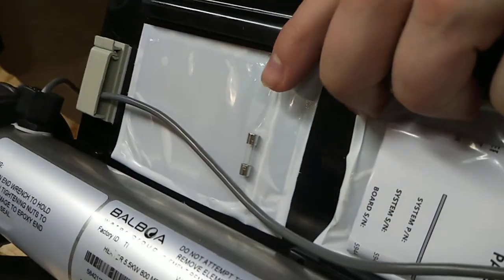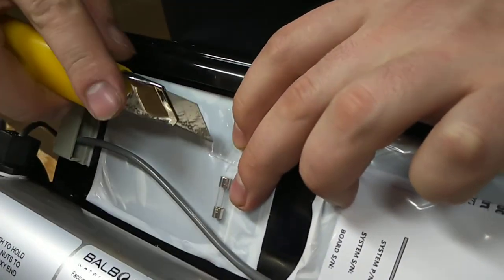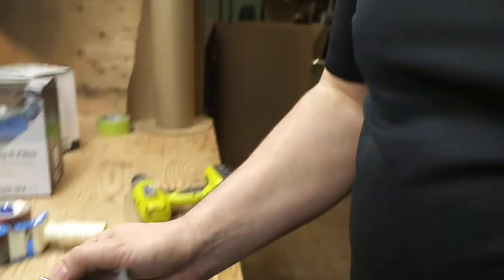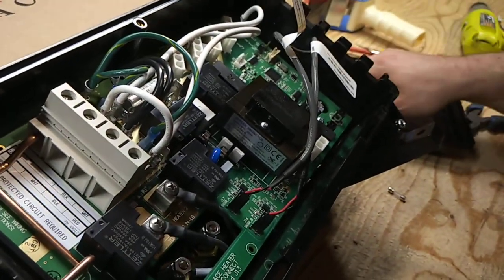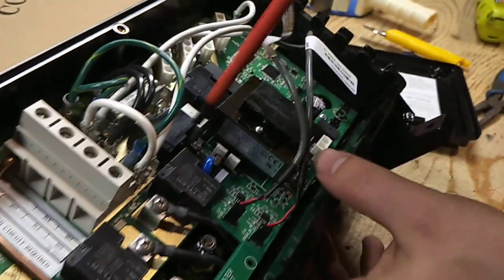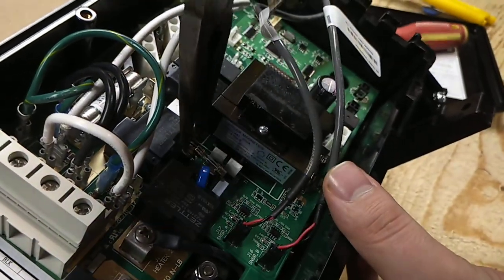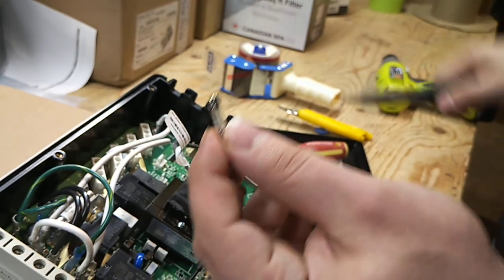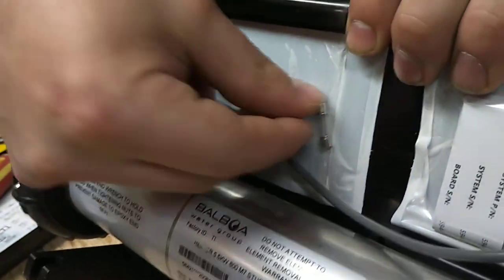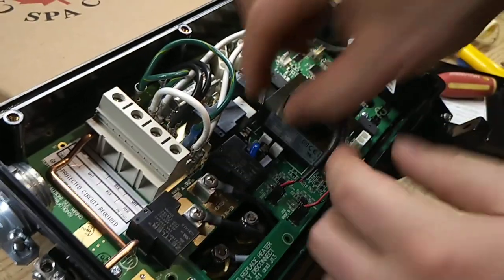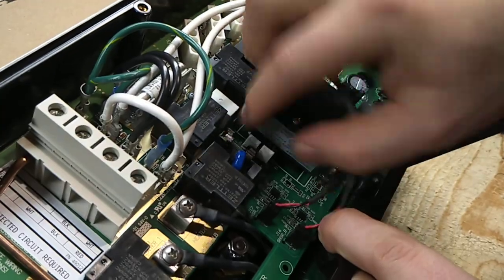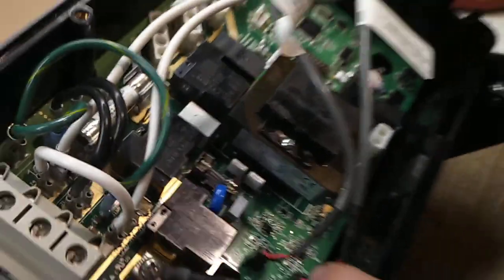So with your new board, you'll have on the back of it located a little fuse. So we're going to just slice this a bit, get access. I'm going to pull this fuse out. They look almost identical. This is a 0.1 amp fuse, and the one that's in here is 0.16. Let's verify that. Yes, 0.16. So you want to replace this small fuse. You can pop this fuse out. You can also use needle nose pliers. Pull this one out. Again, this is the one that's used for 120 volts. And we're going to put this back in this little pouch on the back so we don't lose it. Then we're going to take the 0.1 amp fuse, slide that right in the fuse holder there. There's step number one.